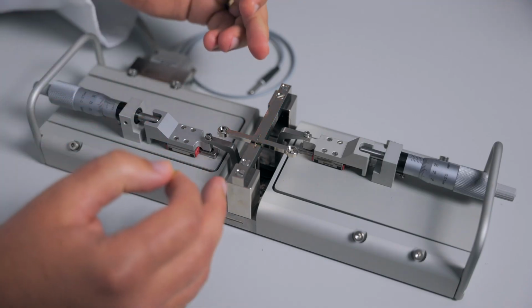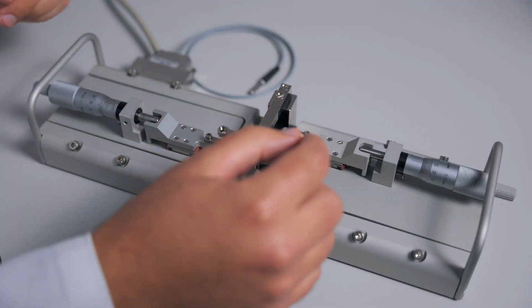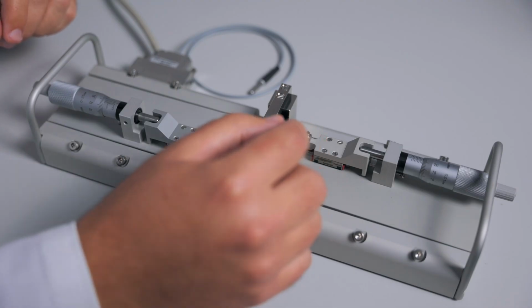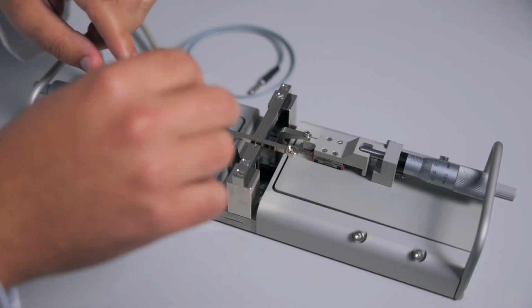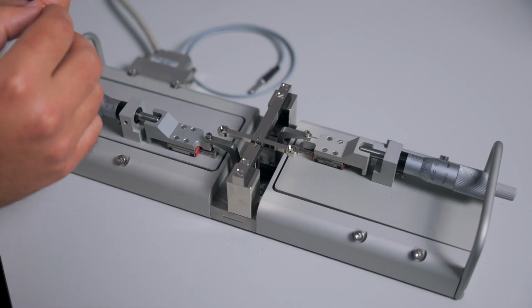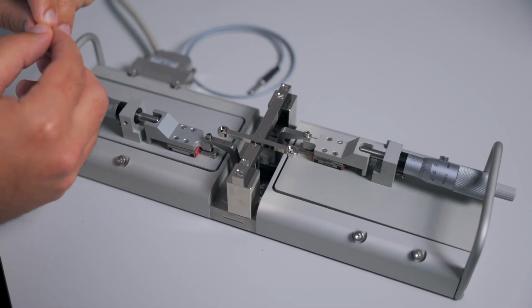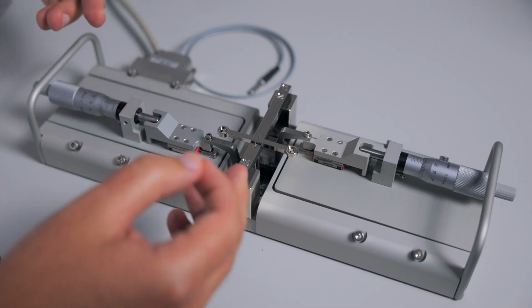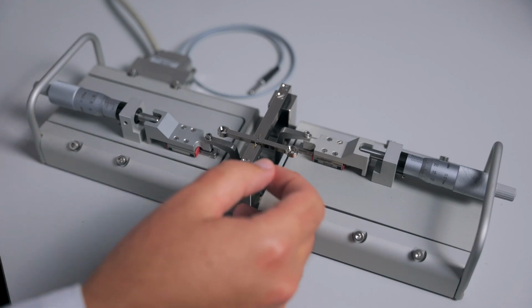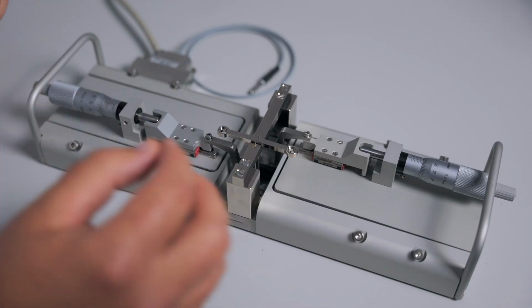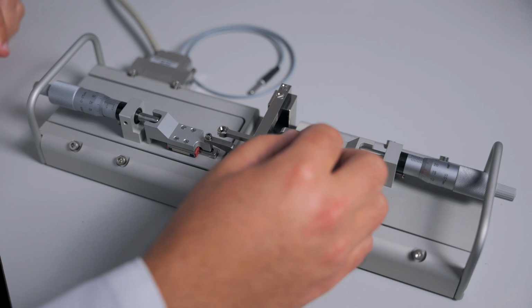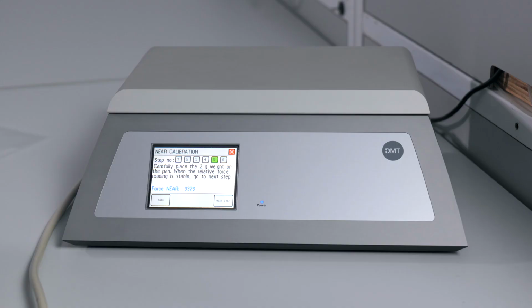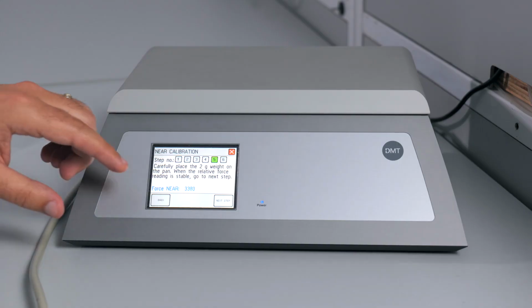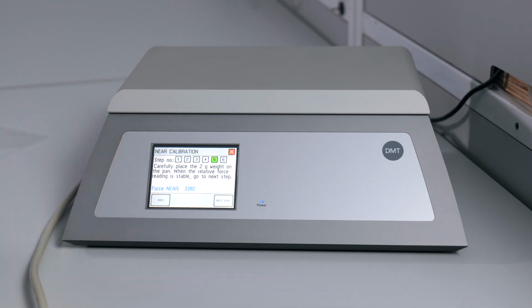Now, whichever side you're doing, you will be placing the weight on the side of the force transducer. This will kick the pin forward and engage the wire, which will simulate a vessel constricting. So in our instance, on the near chamber, the force transducer is on the right side, so we will carefully set the 2-gram weight on the right side. You will give this about 10 or 20 seconds to stabilize before going to the final step.